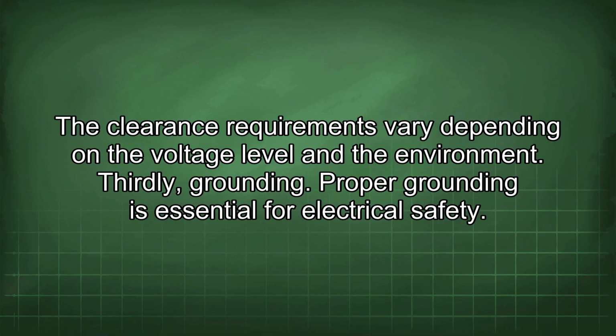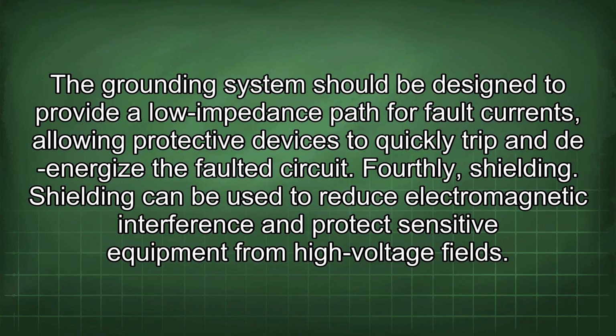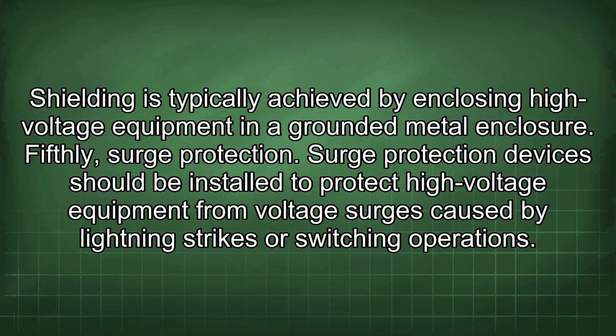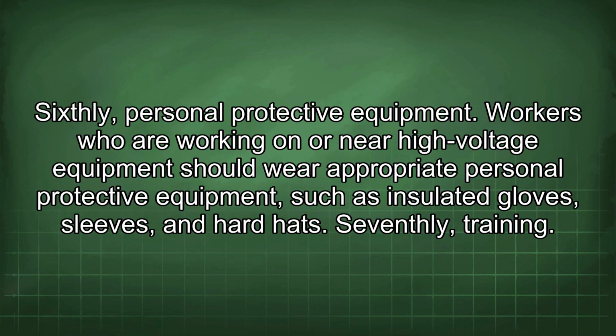Thirdly, grounding. Proper grounding is essential for electrical safety. The grounding system should be designed to provide a low impedance path for fault currents, allowing protective devices to quickly trip and de-energize the faulted circuit. Fourthly, shielding. Shielding can be used to reduce electromagnetic interference and protect sensitive equipment from high-voltage fields. Shielding is typically achieved by enclosing high-voltage equipment in a grounded metal enclosure. Fifthly, surge protection. Surge protection devices should be installed to protect high-voltage equipment from voltage surges caused by lightning strikes or switching operations.